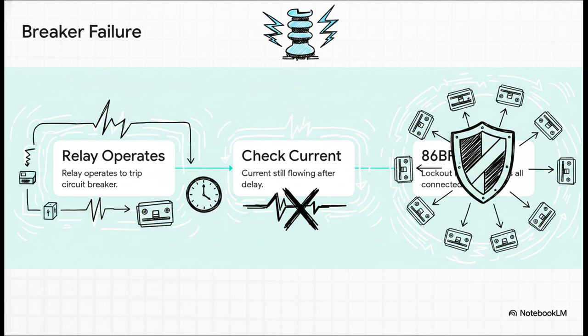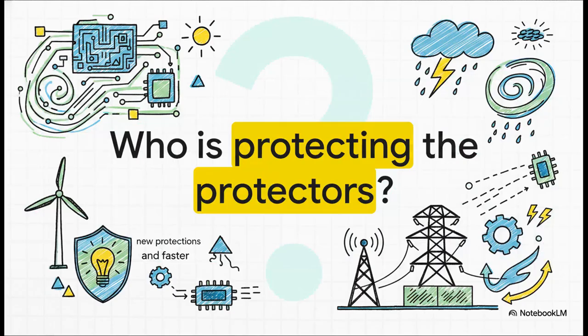This is terrifying, so step 3 invokes the nuclear option, the 86BF lockout relay. It doesn't bother trying the broken breaker again, it immediately sends trip commands to every single other breaker connected to that local substation bus. It intentionally sacrifices the entire local substation just to isolate the massive failure and save the wider grid. It is honestly incredible when you realize that every second of every single day, these invisible layers of logic, math, and high-speed communication are silently watching over our world.